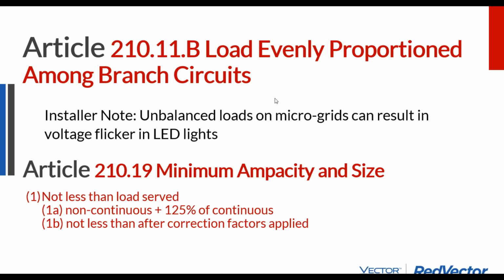Moving on. So Article 210, services, feeders, branch circuits. It says load evenly proportioned amongst branch circuits. Where I have found this balanced load issue to be coming back nowadays is with LED lights. What this means is, in your standard 120/240 electrical service, we say there's two 120 volt legs. They're equally out of phase with each other.